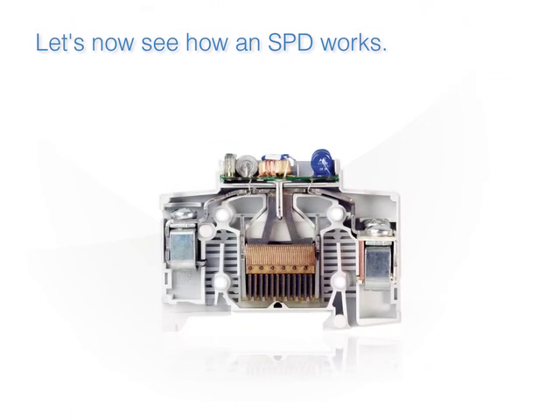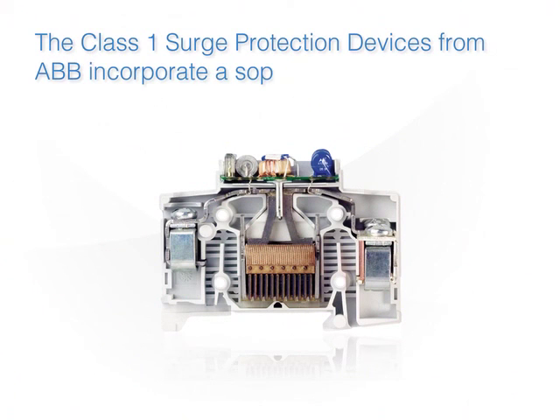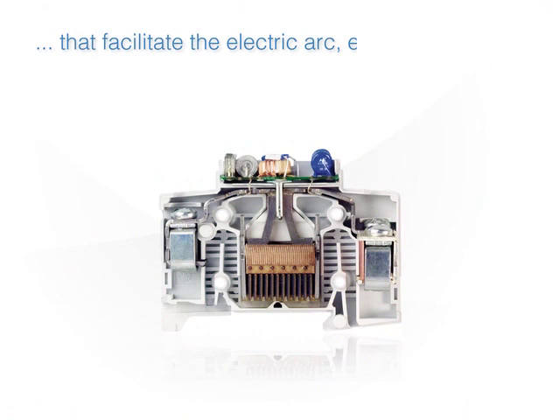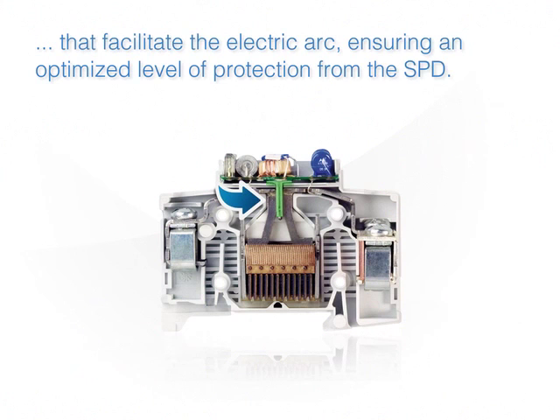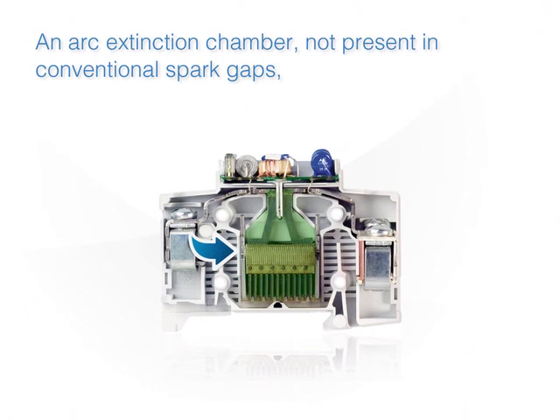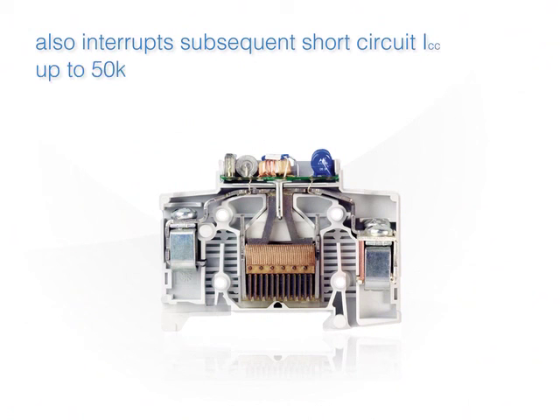Let's now see how an SPD works. The Class 1 surge protection devices from ABB incorporate a sophisticated electronic control system that facilitates the electric arc, ensuring an optimized level of protection from the SPD. An arc extinction chamber, not present in conventional spark gaps, also interrupts subsequent short-circuit follow current up to 50 kA.